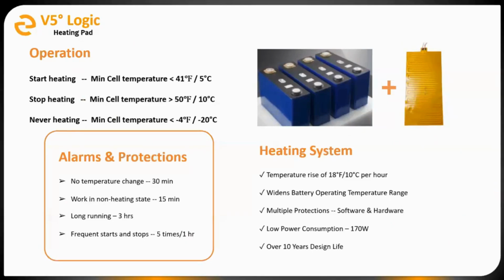At the moment, the heating function requires an external charging source. What that means is that the batteries do not discharge their own energy to heat themselves. They have to have a charge coming in, whether that's from a PV array, a battery charger, a generator, or an MPPT charge controller. It doesn't matter where it's coming from. The battery heating pad itself has a very low power consumption. It's only about 3 amps DC per battery, which is about 170 watts. So you're not going to notice significant side effects in your energy production when the heating pad is in use. It's pretty efficient, I'd say.